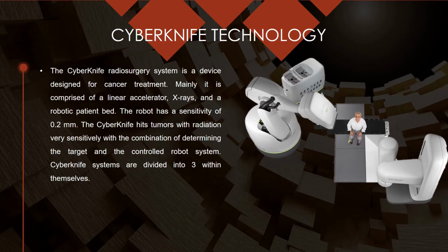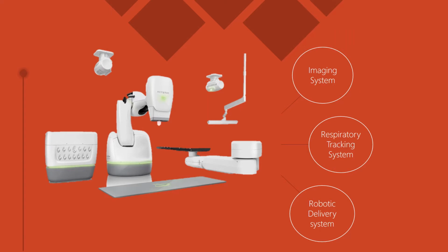Cyberknife technology. The Cyberknife radiosurgery system is a device designed for cancer treatment. Mainly it comprises a linear accelerator that produces 6 MV X-rays, positioned on an industrial robot with 6 joints, and a robotic patient bed that can move in 6 directions. The robot has a sensitivity of 0.2. The Cyberknife hits tumors with radiation very precisely through the combination of target determination and the controlled robot system. The Cyberknife system is divided into three parts: the imaging system, the respiratory tracking system, and the robotic delivery system.